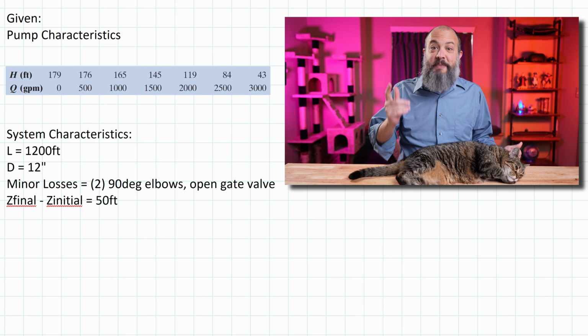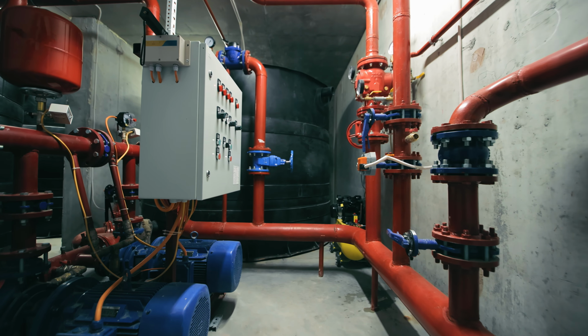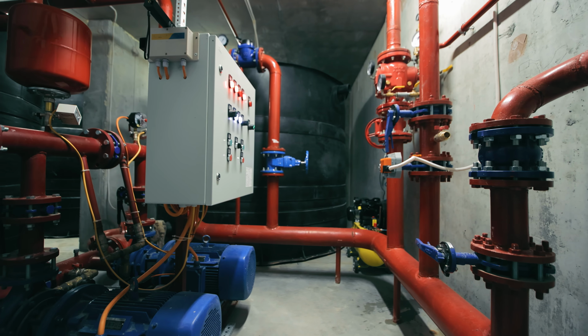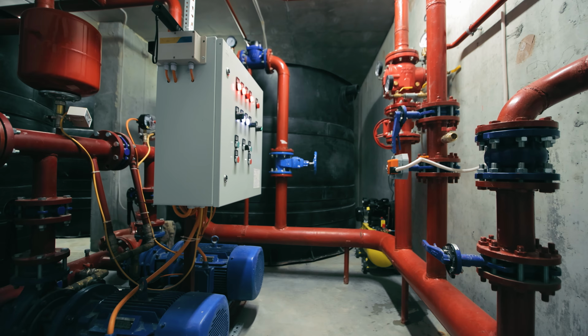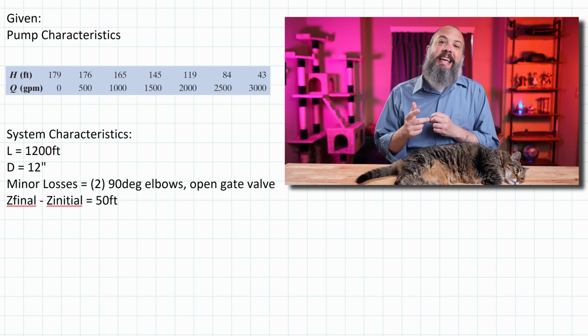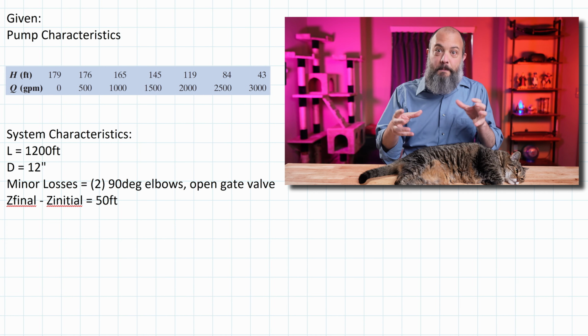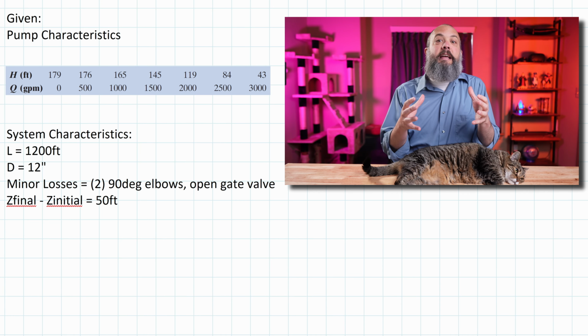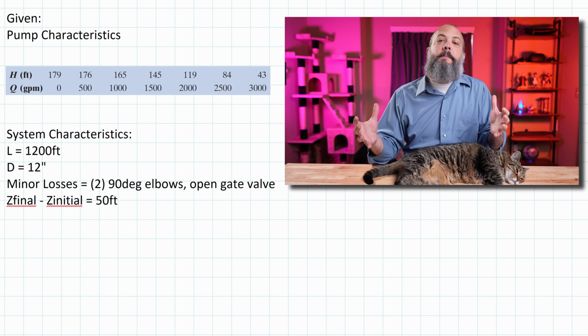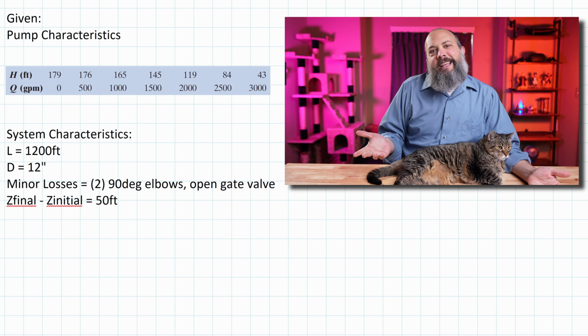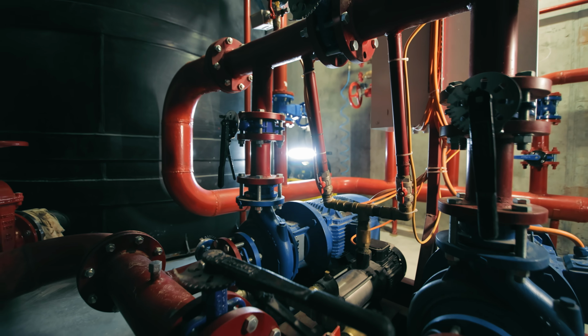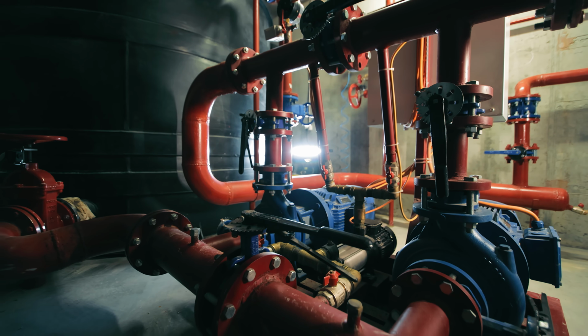Pumps are expensive. So if one small pump won't be large enough, strong enough for your system, sometimes it's going to be cheaper to get two small pumps and combine them instead of spending all the extra money to get one really large pump. Then the question is, should you place your two pumps in series or parallel, which will give you more flow rate or more pump head for your system? And unfortunately, the answer is that it depends. Sometimes parallel will be better, sometimes series will be better.